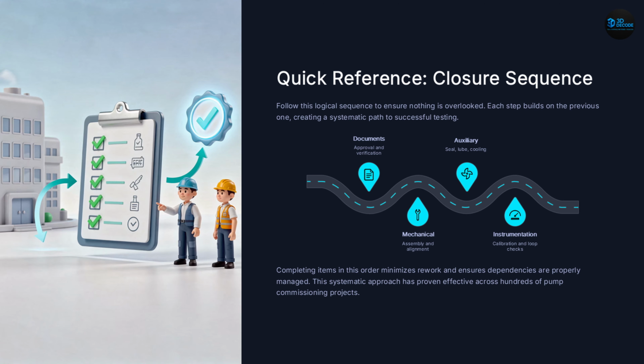Next, quick reference, closure sequence. Before every pump test, remember this sequence: documents, mechanical, auxiliary systems, instrumentation, electrical, then testing. Each step builds on the previous one, and skipping steps creates risk. Successful commissioning isn't about working harder, it's about working systematically, because when preparation is done correctly, testing becomes confirmation rather than troubleshooting. And that's exactly how world-class commissioning teams operate.